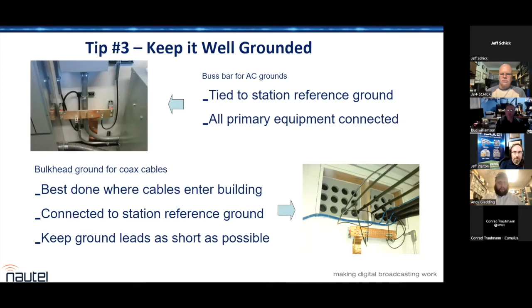Talking about how we connect things, I'm going to say this now, and I'll probably say it several more times in the next half hour or so. I hate compression connections. Anytime you have a stranded wire in a compression connection, whether it's a ground clamp going to a ground rod, or a stranded wire into a circuit breaker, it's going to work loose. It's not a matter of if, it's a matter of when.